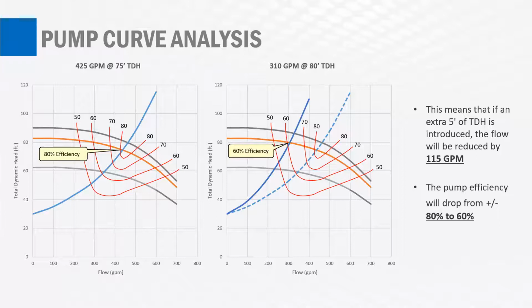What you can also see there in those red curves where you see 80, 70, 60, and so forth, that's pump efficiency. So the original pump curve and system curve that you see on the left, that pump efficiency is around 80%. That's a pretty good pump efficiency. But you can see with the curves on the right, that efficiency can drop pretty quickly. For this particular pump, with just an extra 5 feet of total dynamic head, the flow is reduced by 115 gallons per minute.